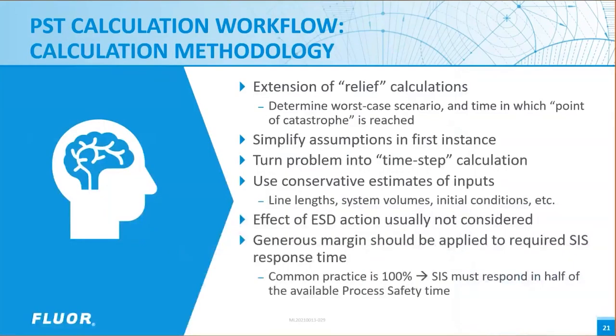But in any case, once you've defined your point of failure, you can now do a calculation around that. So in the first instance, we want to do a simplified rendition of the calculation. So we're trying to identify usually the worst case flows in and out of a system and the worst case starting conditions. And we want to apply simplifying assumptions that allow us to turn that calculation into almost like a time step calculation, something that can hopefully be done in a spreadsheet.